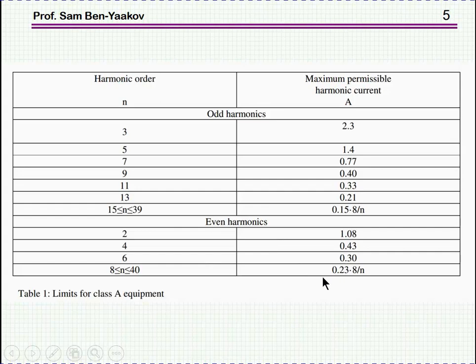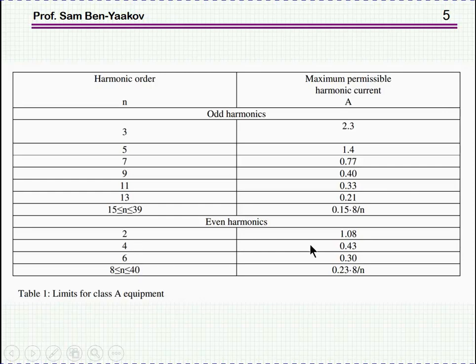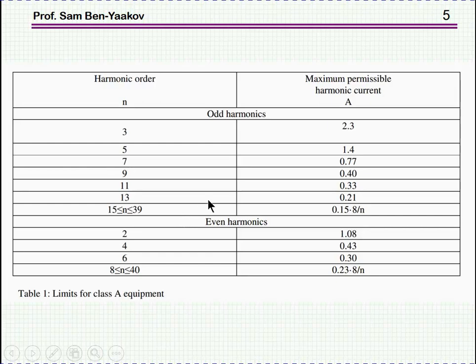Here is the table for class A. We see the harmonic order and the maximum permissible harmonic current. The third harmonic is 2.3 A, the fifth harmonic is 1.4 A, etc. For even harmonics, there are also some limits. Usually, if it's a balanced rectification, you will not have even harmonics, but limits are defined if they occur. 2.3 A is a fairly high current, so if the piece of equipment is low power — say 200, 300, or 400 watts — it's not that difficult to meet this standard. However, if the total power of the equipment is one or two kilowatts, then it becomes a little bit more difficult to meet the regulation.